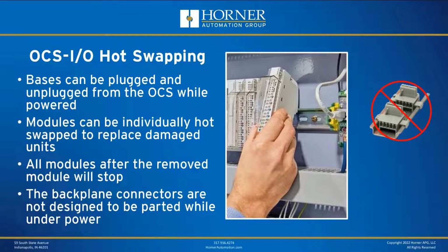It was designed to support what's known as hot swapping. In other words, pulling a module out from the front while powered up. Now, when you do that, the modules on the left of the removed module will work as normal, and the modules on the right will pause until the new module is inserted. So that's how that works.